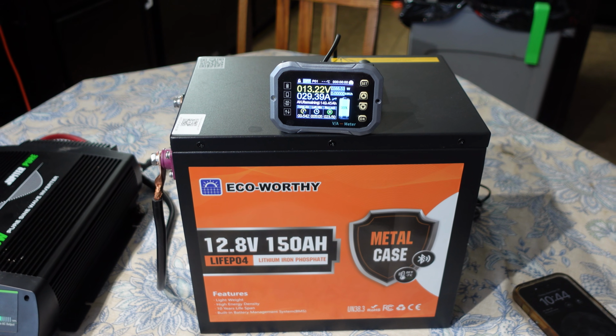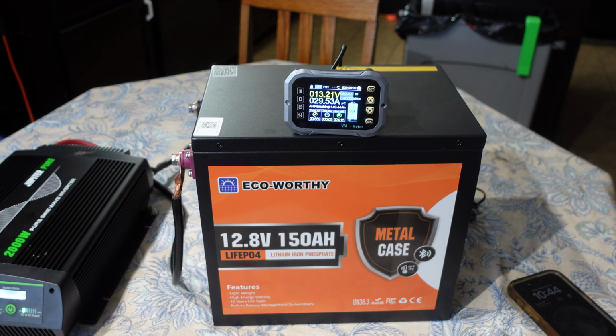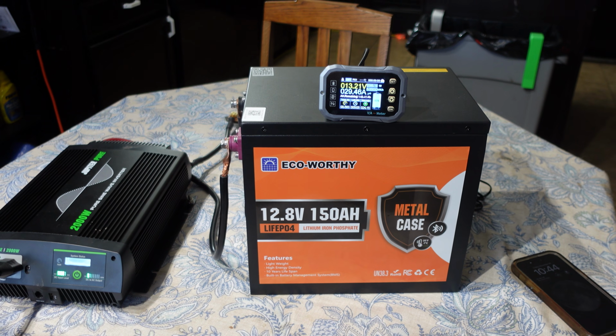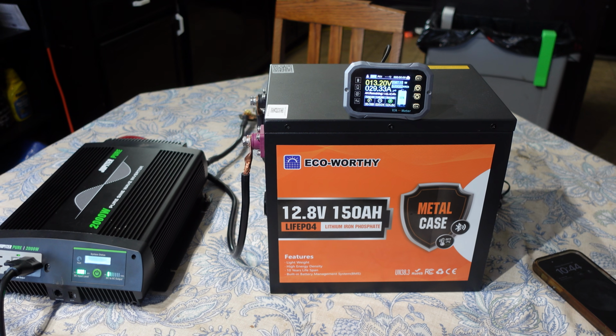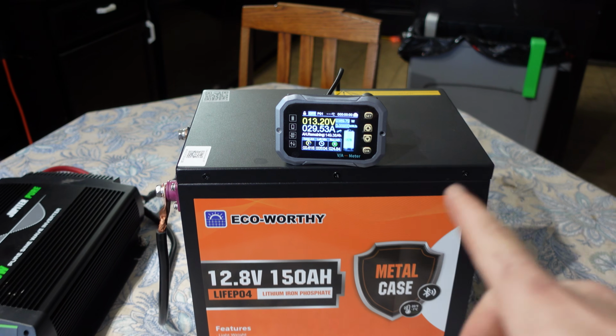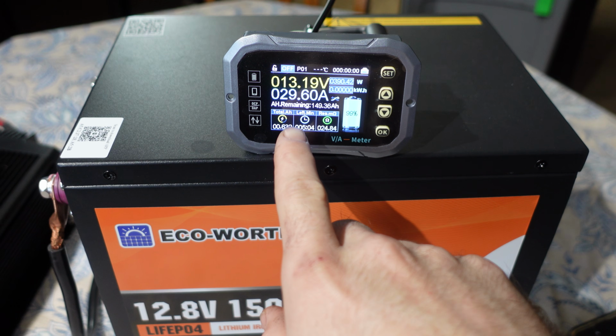There's our 0.2C load, about 30 amps, as close as I could get it. So we're gonna let this test run all the way through until either the battery shuts down or the inverter shuts down, whatever happens first, and we're gonna be able to see our final capacity number right there.